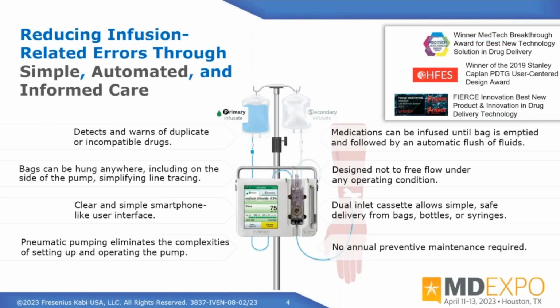We'll actually pump all the way down the tubing line and into the chamber. Once an air bubble hits that diaphragm that I talked about, the device senses that. It will kick the air bubble back up, and it will alert the nurse that the bag is empty, or it will kick over and push the primary fluid through for a flush. Okay, so a lot of technology, a lot of intelligence of design went into the product.